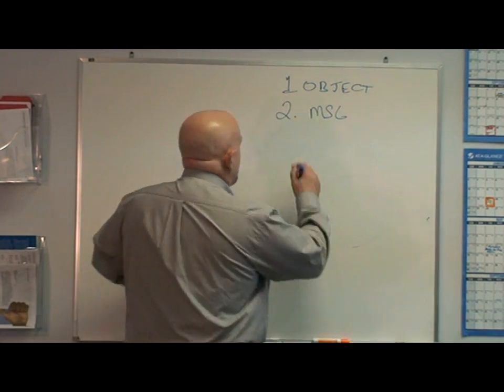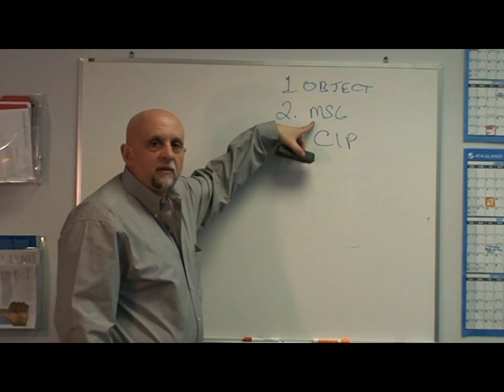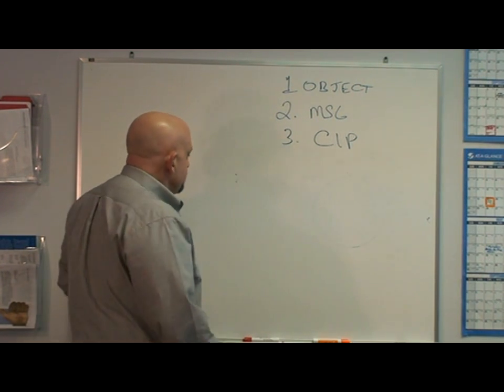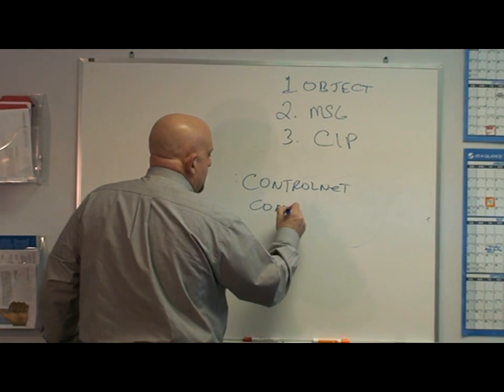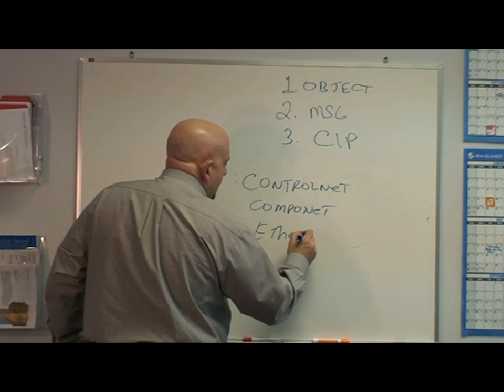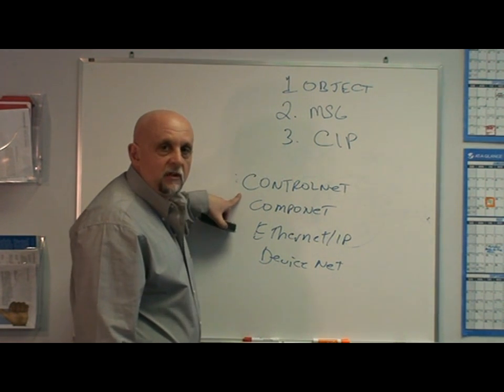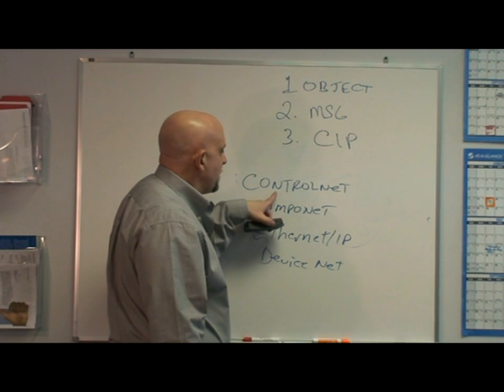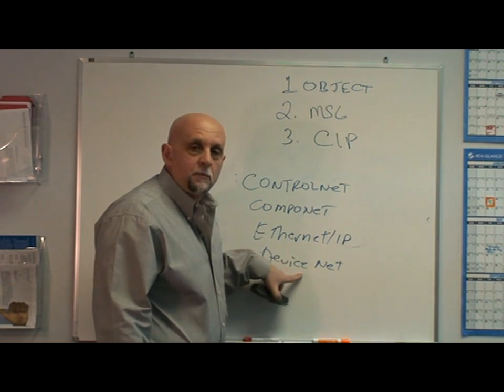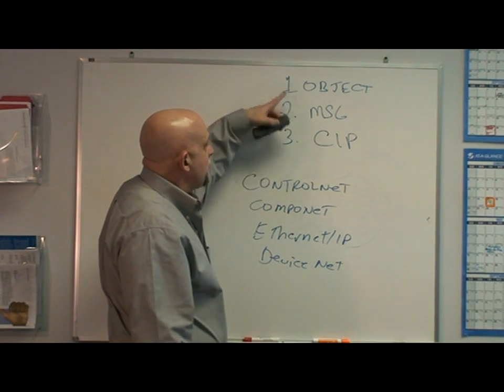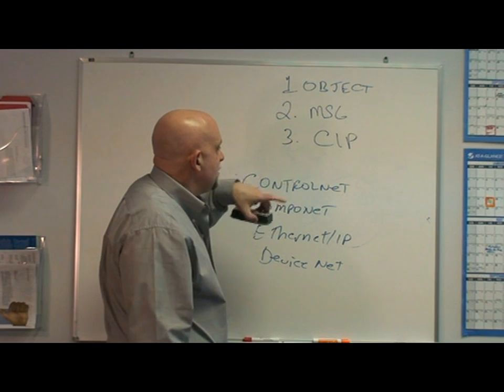The third thing you should know about DeviceNet is that it's part of CIP — the Common Industrial Protocol. This object-based structure and messaging is what CIP is. It's the same for ControlNet, EtherNet/IP, and DeviceNet — all use the same object-based structure and the same explicit and implicit messaging. When you send those messages over the ControlNet physical wire, you get ControlNet. Over Ethernet, you get EtherNet/IP. Over CAN, which is the basis for DeviceNet, you get DeviceNet. CIP is the core for all of these, and it is owned and maintained by the ODVA.